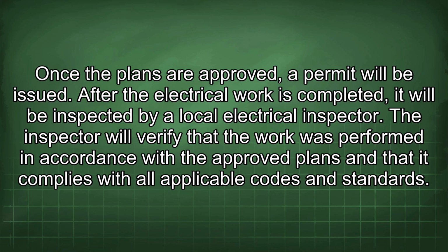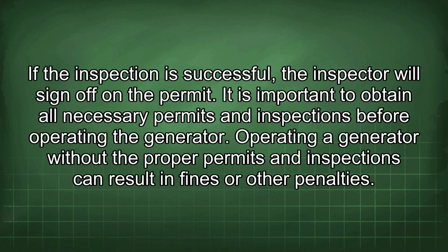After the electrical work is completed, it will be inspected by a local electrical inspector. The inspector will verify that the work was performed in accordance with the approved plans and that it complies with all applicable codes and standards. If the inspection is successful, the inspector will sign off on the permit. It is important to obtain all necessary permits and inspections before operating the generator. Operating a generator without the proper permits and inspections can result in fines or other penalties.